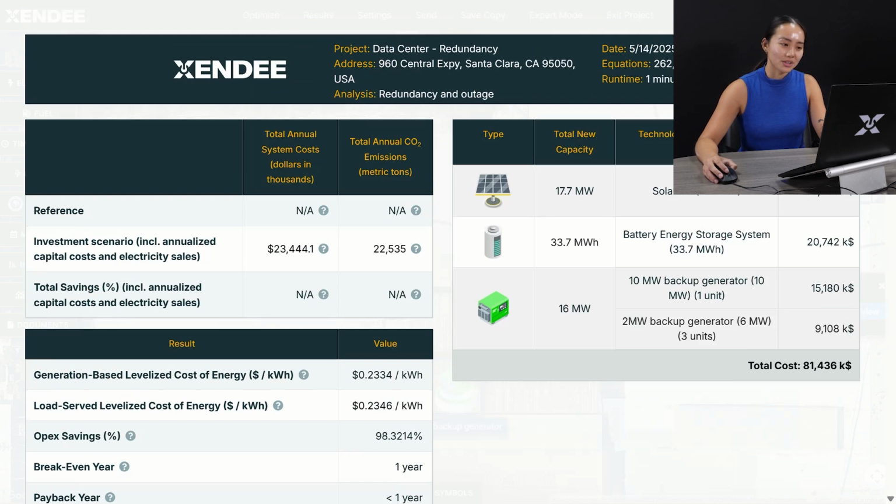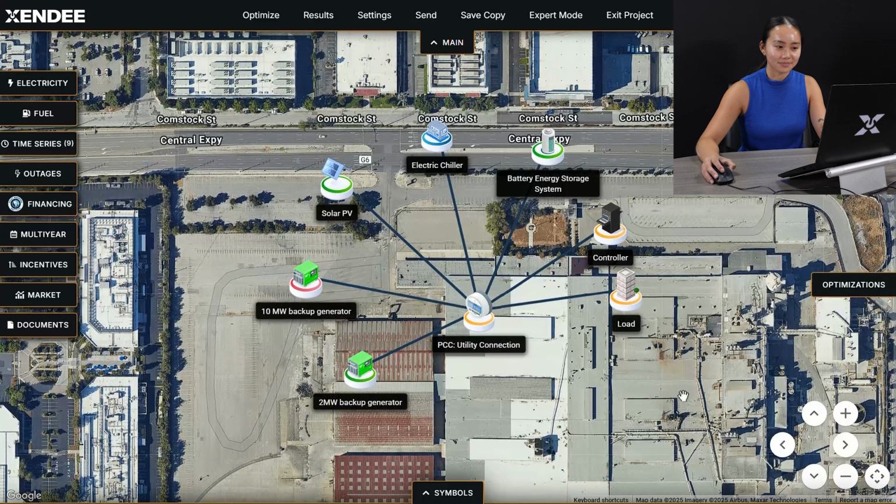In this approach, our large on-site battery capacity enables us to achieve 100% electric redundancy with only installing a fraction of the backup generator size. This results in a more cost-effective and flexible system instead of the typical N+1 planning method. So there you have it.